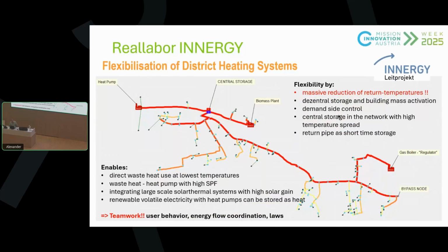So here is an example, close to the Innsbruck network, where we do, for example, simulations, but just again to summarize the important points. To get flexibility, the most important part in the network is a massive reduction of return temperatures, because, as I said, then I can increase the power and I can reduce the losses. But this also means I can use decentralized storage systems and building mass activation much more, especially storages. Again, the same: if I have a low return temperature, then I can cool down the storage much more. And in the same volume, I get immediately 30, 40, 50% more heat capacity, which I can use.